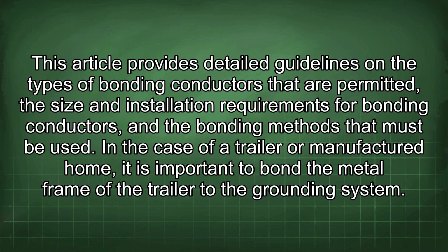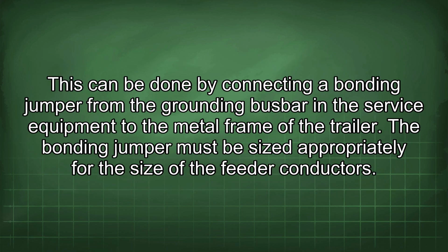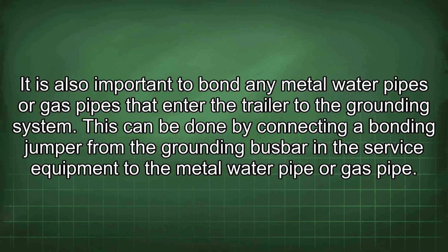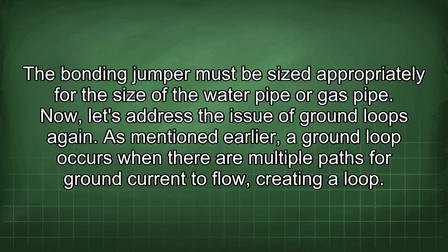In the case of a trailer or manufactured home, it is important to bond the metal frame of the trailer to the grounding system. This can be done by connecting a bonding jumper from the grounding busbar in the service equipment to the metal frame of the trailer. The bonding jumper must be sized appropriately for the size of the feeder conductors. It is also important to bond any metal water pipes or gas pipes that enter the trailer to the grounding system. This can be done by connecting a bonding jumper from the grounding busbar in the service equipment to the metal water pipe or gas pipe. The bonding jumper must be sized appropriately for the size of the water pipe or gas pipe.